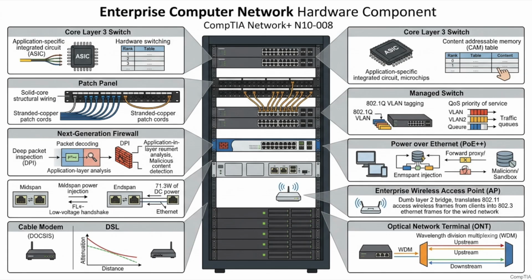It's an excellent stopgap. The key engineering constraint to remember there, though, is backward compatibility. A brand new PoE++ switch can easily negotiate down to power a 15-watt legacy desk phone. But it doesn't work in reverse. Exactly. An older PoE switch physically cannot push enough amperage to boot up a modern 70-watt device. Makes sense.